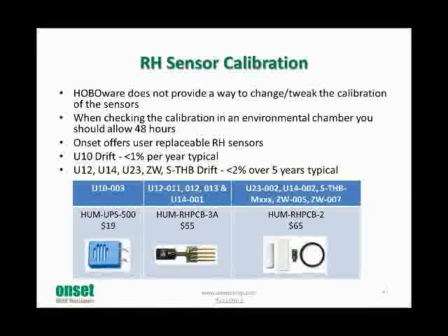The sensor - we use the same sensor here for the U12s. All of these products are the same sensor essentially, which is a digitally calibrated sensor. They do drift over time. The one for the U10, actually, if this for whatever reason does get wet, we do recommend replacing it right away. But the rest of these are user replaceable. And you'll probably, depending upon your environment, how harsh it might be, want to replace your sensor every 2 to 3 years or something along those lines.